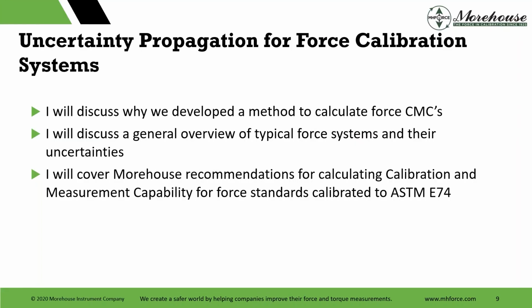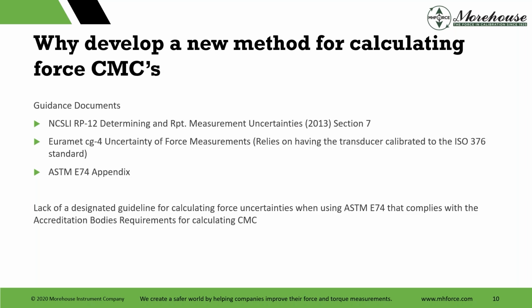So other things, I'm going to discuss why Morehouse developed a method to calculate force CMCs, a general overview of typical force systems and their uncertainties, and recommendations for calculating calibration and measurement capability, which sometimes I'll say CMC. That is what I'm talking about, calibration and measurement capability. So why go to this effort?